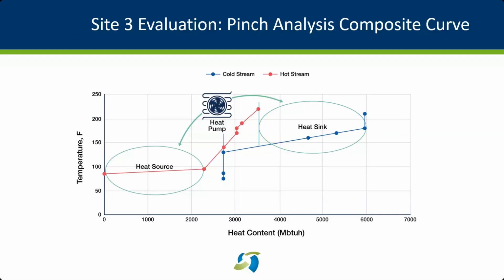This shows the pinch analysis curves for a particular site. The green circles show the potential for a heat pump. So we're looking at heat available at lower temperatures and how we could move it up to a higher temperature to use it for heating the cold stream. The heat pump would take the energy rejected at the lower temperature and deliver it at a higher temperature to meet process hot water or steam needs.